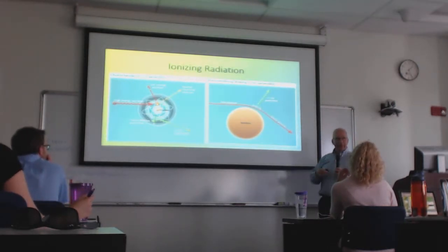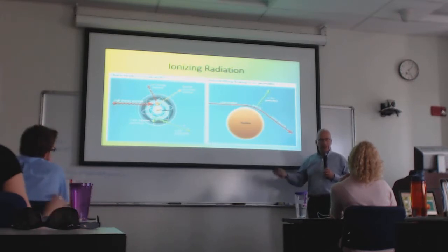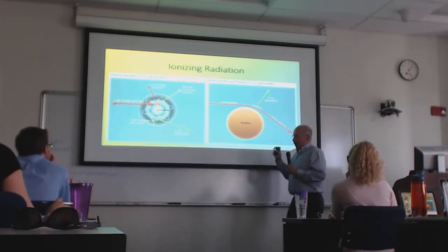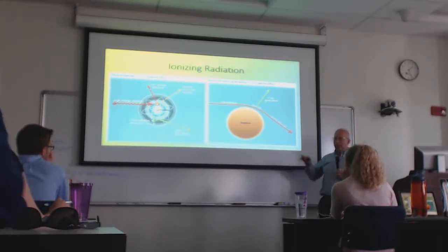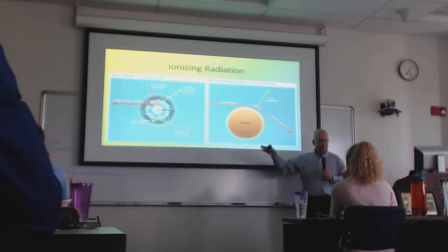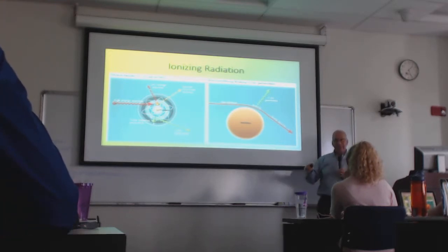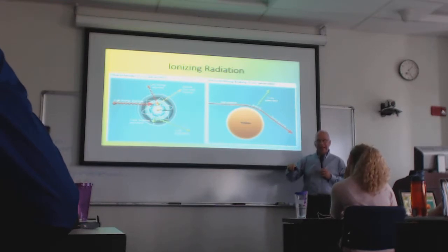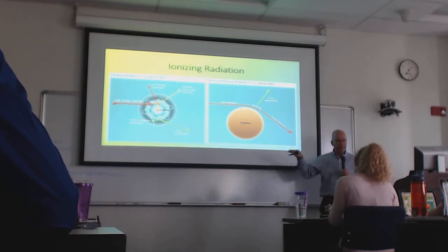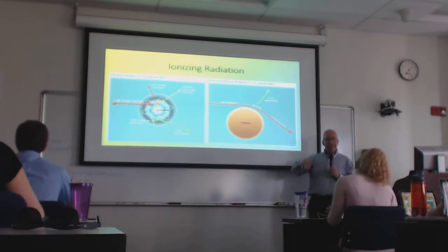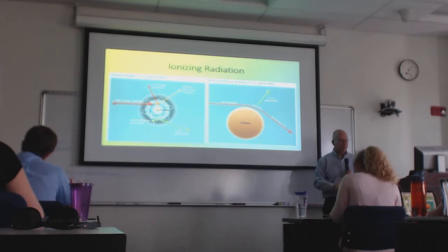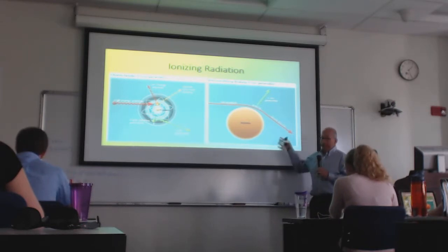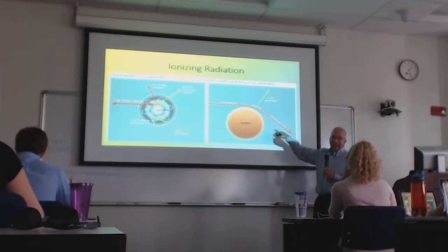So what happens inside the tungsten or the molybdenum to actually cause an X-ray to be made? There are two kinds of X-rays formed. One is called characteristic radiation, and it's called characteristic because it's characteristic of a specific element that is being bombarded with the electrons. So the X-ray energies coming out of tungsten would be different than the X-ray energies coming out of molybdenum or something else. And then the other kind is called Bremsstrahlung, or braking radiation.